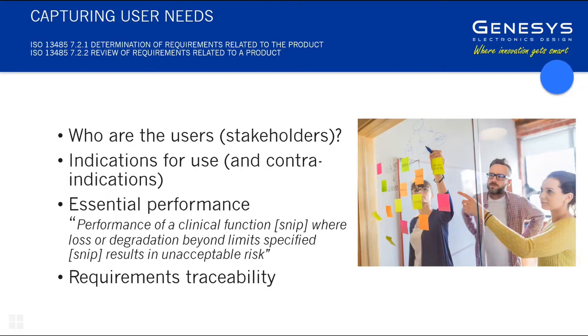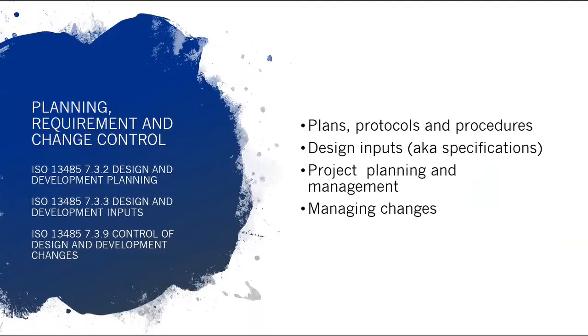Other people use large tables, with all the requirements in great big tables. If you do that, you rapidly lose intelligibility for someone who just wants to understand what the needs are, if it's just a big amorphous table full of requirements. So there's no perfect way to skin a cat, but at the end of the day, you do need to have that traceability in place. And I would advocate giving every requirement at every level in the documentation hierarchy an alphanumerical code that is then cross-referenced to provide the traceability. Sure. Okay, let's move on.